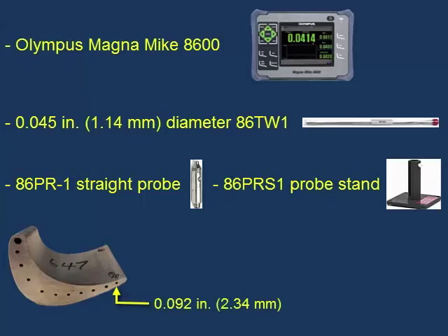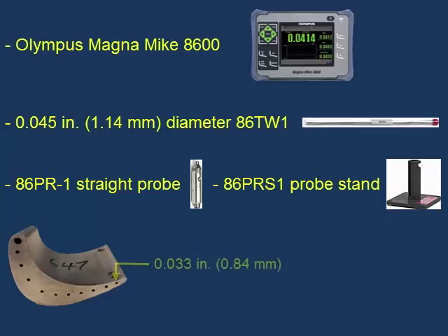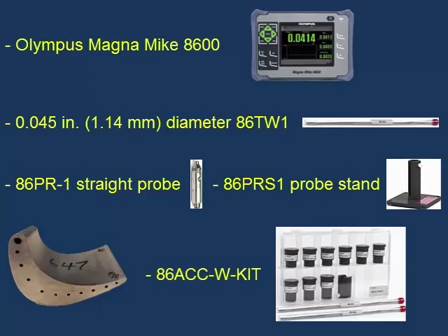The thicker side is about 0.092 inches or 2.34 millimeters. The thinner side is about 0.033 inches or 0.84 millimeters. We will be using the 86ACC-W- kit, which includes the target wires, as well as wire on fixtures and reference standards designed to be used with the wire targets. We will be using the Magna-Mike in an area free from interference from magnetic materials.